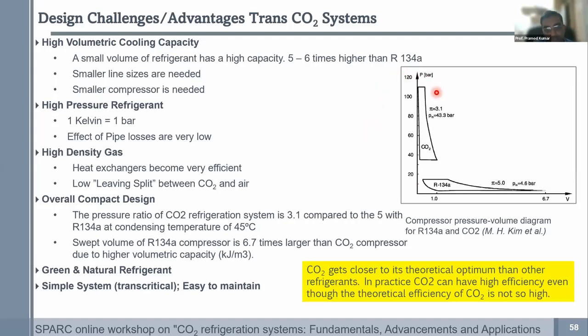But that only means that you need to elevate your workmanship when you build the systems. Another advantage, and this is where we have seen firsthand experience, is that CO2 gets very close to your theoretical predicted COPs. So you don't have to have a scaling factor like with 134A, where you say it will perform at 80% of my theoretical predicted efficiency.